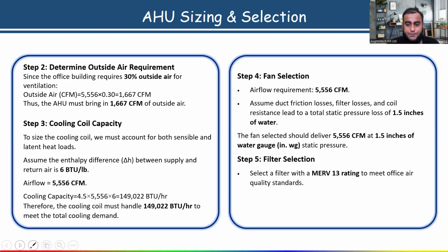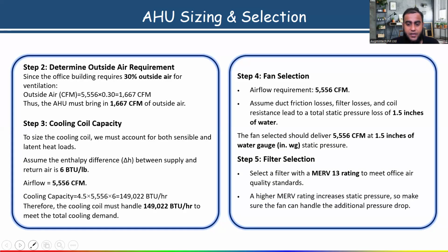Then filter selection. All of you know, here we are talking about an office building. So we have to select a filter with a MERV 13 rating to meet office air quality standards. Clear? That I have discussed in detail. A higher MERV rating increases static pressure, so make sure the fan can handle the additional pressure drop. So these are the details which you have to submit to the manufacturer. Once you submit these details, the AHU manufacturer will give you this data.